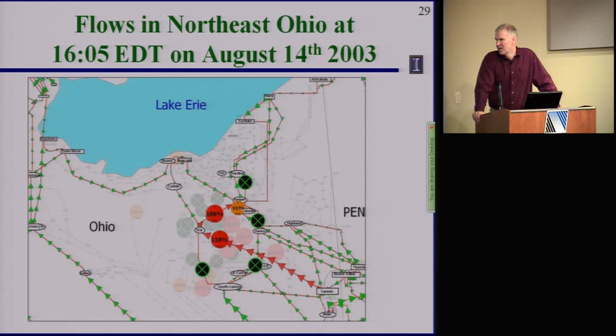But when the Sammis-Star line popped at 1605, then stuff really started to go fast. Now we have low voltages spreading across the region. Of course, if you know much about power, you know that power is equal to voltage times current. So as the voltage goes down, the current goes up. And as the current goes up, the resistive losses are I squared R. Current goes up, I squared goes up with the square of current. The lines start heating up more and more.